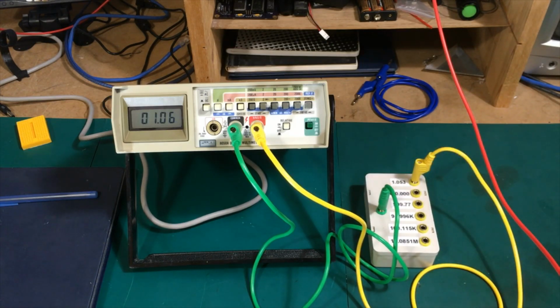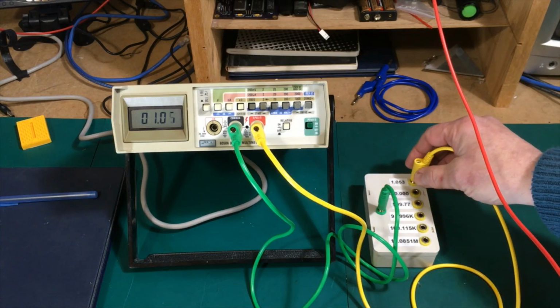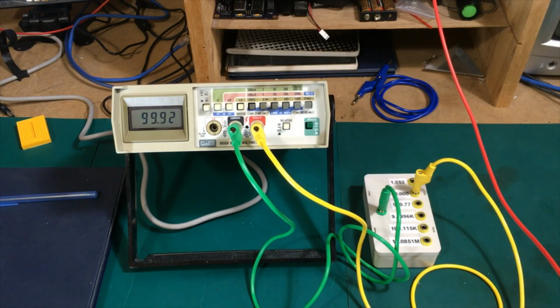So for this first one, for that first resistor there, that 1.053, so anything between 1.01 and 1.09 on the meter would be acceptable. So let's see what we get there. Okay, 1.06. Well, that's definitely right in the middle of that range, so I'm delighted with that. Let's go on up to the next one. We'll also do this on the same range, this 100 ohm resistor, because we're still on the 200 ohm range. So anything from 99.86 to 100.14, and again we're smack dab in the middle of that range. So that's great. Things are looking really good.